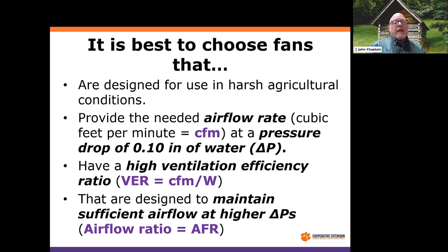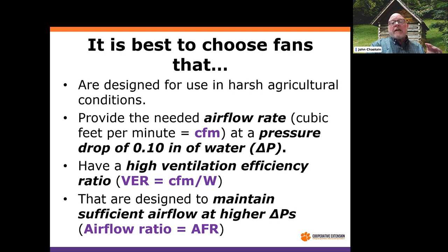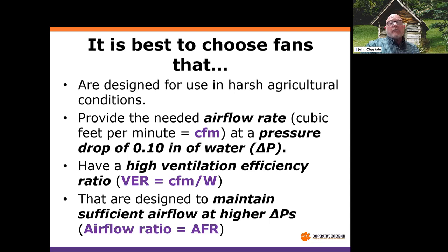The next criterion is airflow rate. We need to make sure the fan we're choosing provides the airflow rate we need. The recommendation is to select a fan that will give us the airflow we need at one-tenth of an inch of water static pressure. We may use that fan at a slightly higher or lower static pressure, but that's the criterion we use for fan selection.